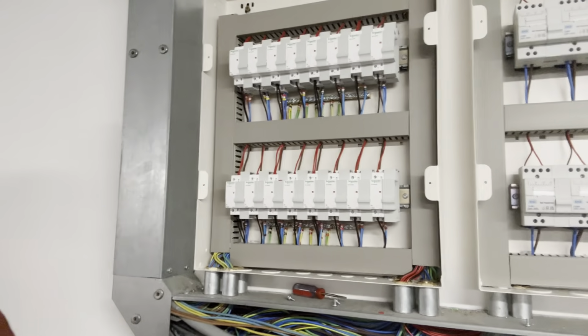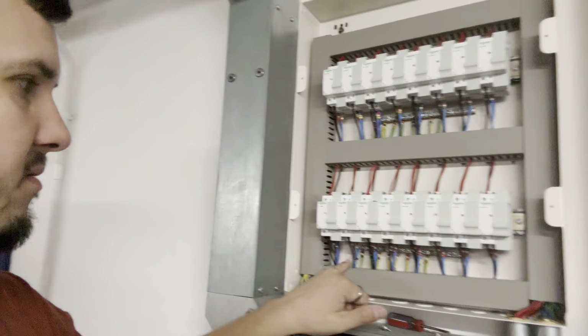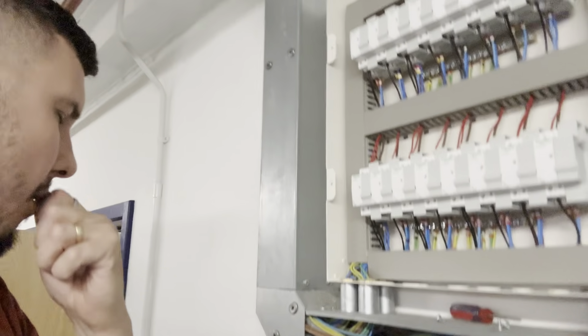It's the next day, by the way. Half of that row did not come on because one of my negatives had come loose in the contactor, so I replaced that. It was at that point I realised I'd made a very stupid mistake. It's been a horrifically long week, very long hours, and I'm very tired. One thing I didn't quite think about properly was that I was switching the neutral through my contactor. So this morning, it took me 40 minutes, I literally whipped the neutrals out the top of the contactors and doubled them up in the bottom here.